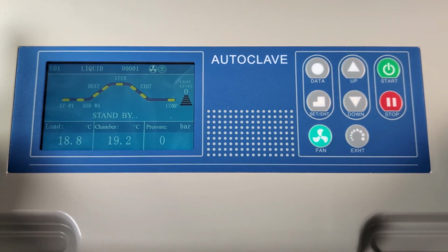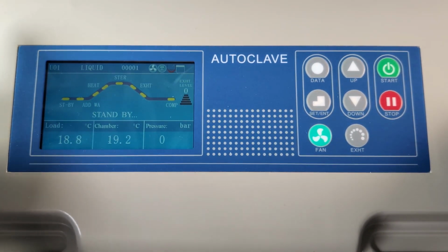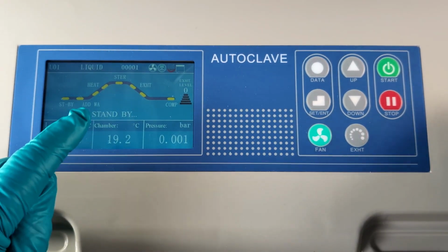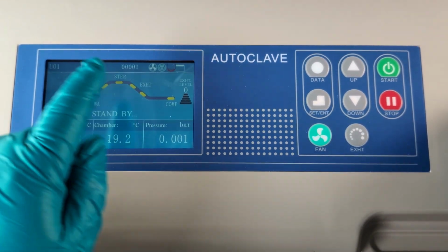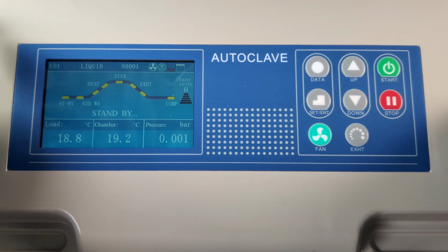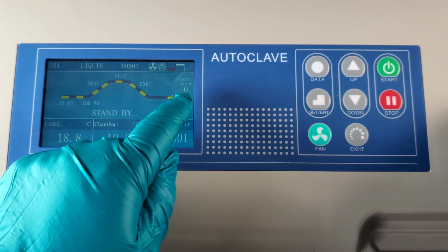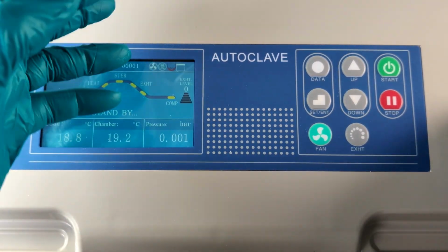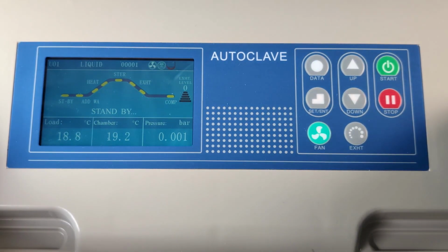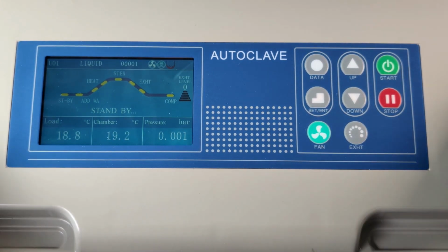Once the sterilization time is over, on this occasion it's set at 20 minutes, you get to the exhaust stage. At this point, the vent opens behind the autoclave and the steam is expelled. That gets you down to atmospheric pressure, and then you can start cooling. And when you're cooling, then when you get to 80 degrees in this case, you can open the lid.